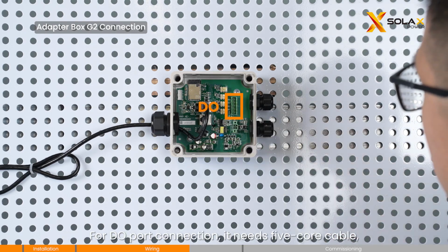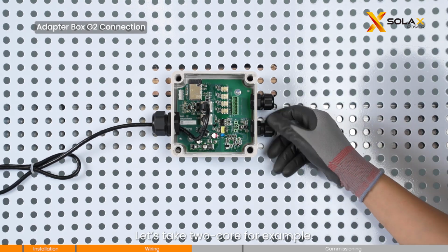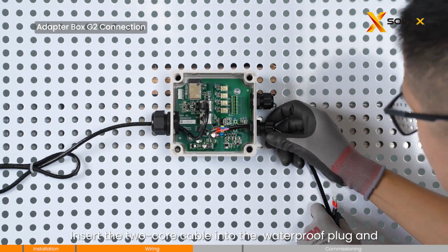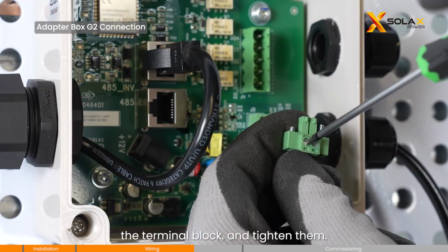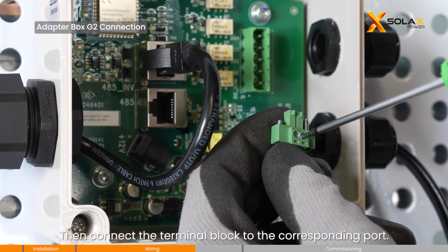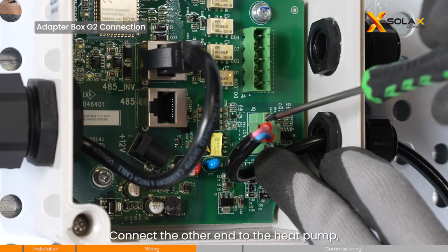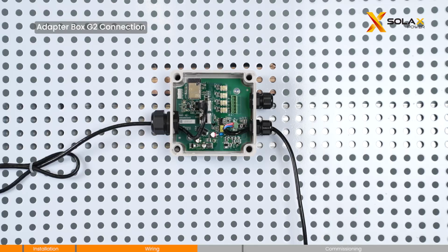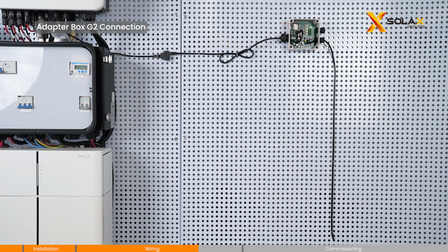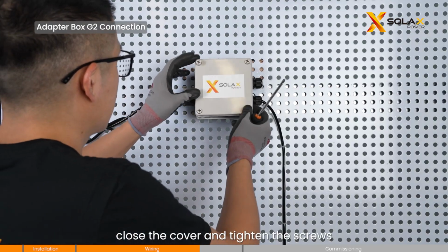For DO port connection, it needs 5-core cable, and AO port 2-core cable. Let's take 2-core for example. Insert the 2-core cable into the waterproof plug and the terminal block and tighten them. Then connect the terminal block to the corresponding port. Connect the other end to the heat pump. Close the cover and tighten the screws.